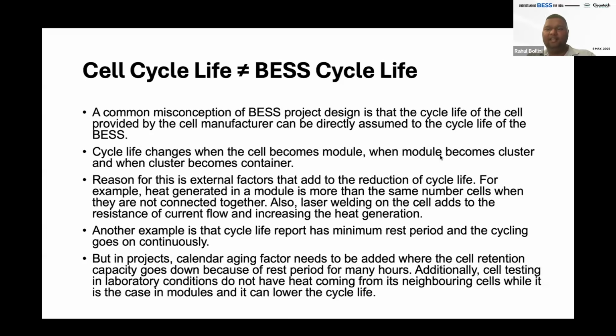Whatever said and done, and cells are manufactured in a way, one must understand that in a liquid cooling unit, the input of the liquid cooling, where it goes in, those cells are cooler than near the output of the liquid cooling coming out. So the cells near the output will degrade faster than the input side. So balancing issues will come eventually. After the first 2 years, you will start seeing small degradation issues. And also one must understand that the degradation of LFP cells, at least in the first 2 years at a system level, is very high. First year being the highest, second year being second highest, and then it pretty much flattens out. So that's how it is.